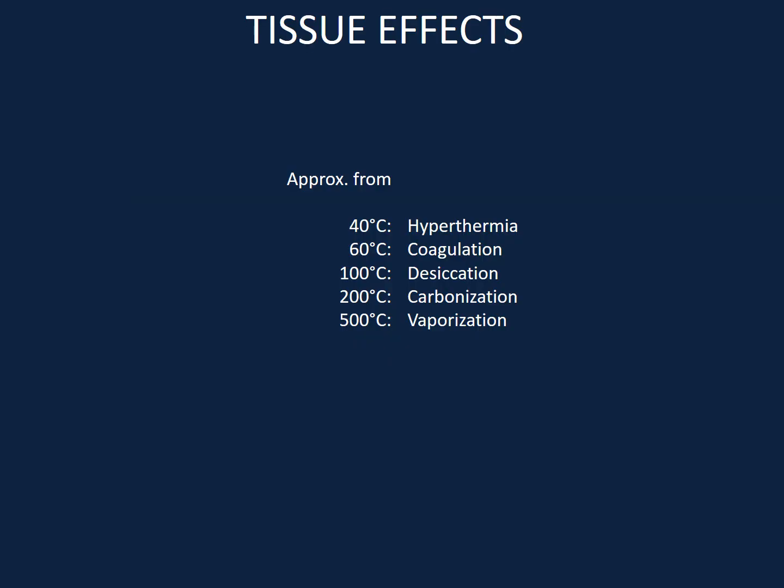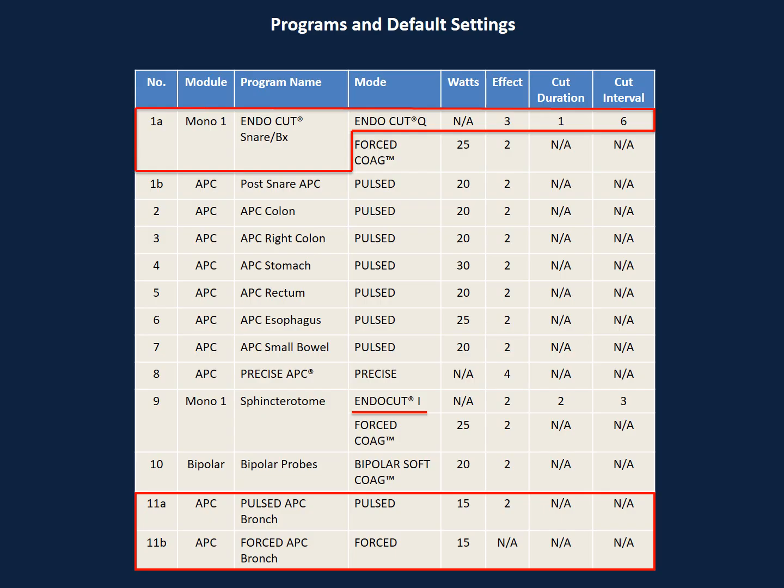The degree of thermal effects depends on several factors: the application duration, the power setting, the probe distance, and other factors like the type of tissue. The programs used in the airways are the EndoCut and the argon plasma coagulation. Their use is based on what we are trying to achieve — cut, coagulate, or both. The default settings are based on evidence-based practices; however, the physician is responsible for choosing the appropriate equipment, instrumentation, and settings to effectively treat each patient. The lowest possible setting should be used to achieve the desired end effect.